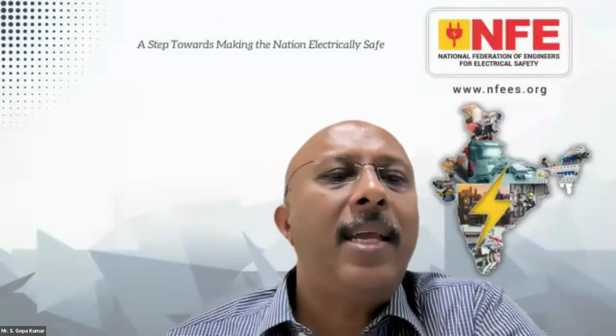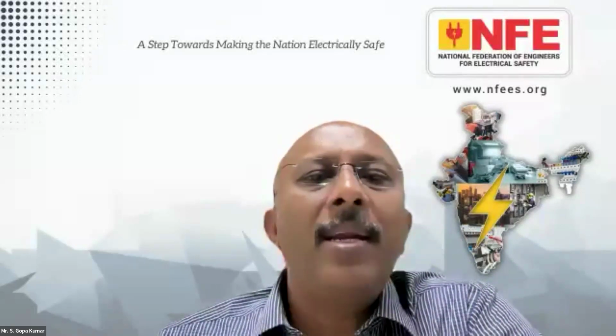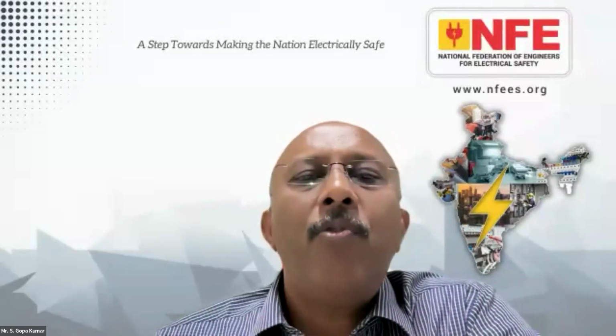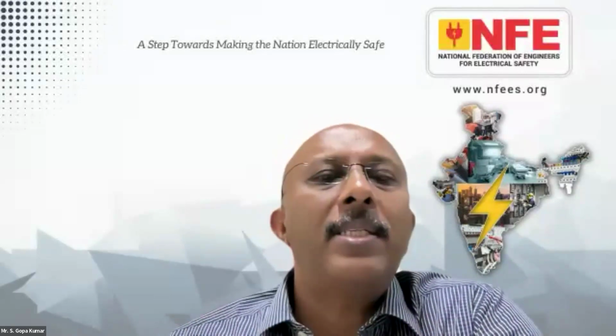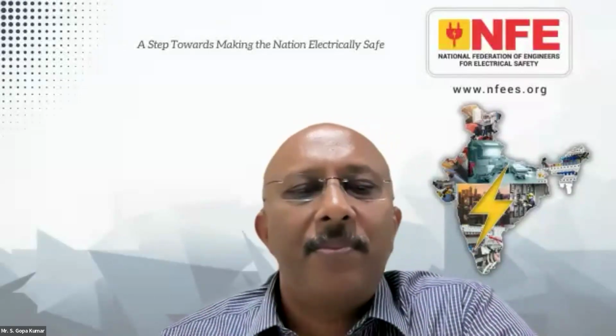Mr. Kiran Joshi is asking, are the quality of earthing and fault loop impedance related? If yes, how? If not, how can fault loop impedance be improved in spite of all connections at the building side being firm? Yeah, so Mr. Joshi, as you must have seen in the presentation on some of the slides, we mentioned that first you have to do the earth fault loop impedance test. And if the fault loop test is not passing, it means the fault loop impedance value is higher. And you should take measures to bring down the fault loop impedance values. And the right approach is to start right from the designing stage and not at the implementation stage.